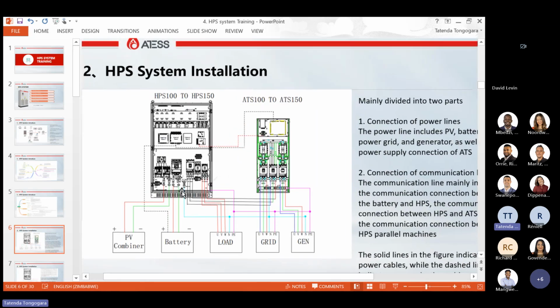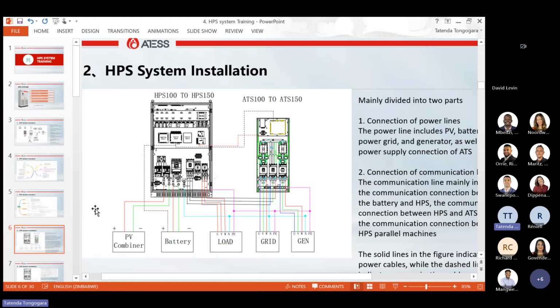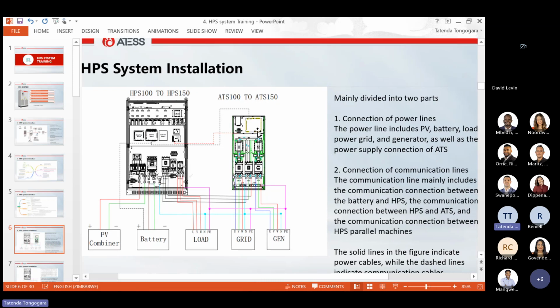Okay, so our HPS, we have a range from HPS 30, 50, 100, 120, and 150. These HPS systems can be paralleled up to 4 units. So the maximum you can get from an HPS is a 600 kilowatt system. So our HPS is divided into two parts, mainly two parts. We have the power side and then the control side.